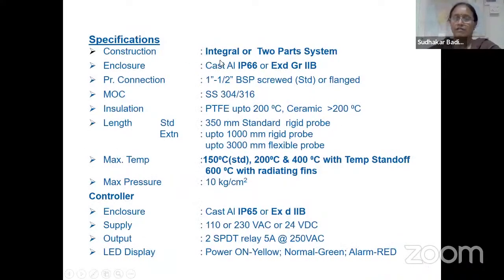It is available in two constructions, that is integral and two part systems. The picture which we saw is of the integral type. It means the electronics is on its head itself, and in the two part system, the probe will be different and the electronics, or control unit, will be different. The enclosure is IP66 or X-proof 2B. The process connections can be screwed or flange connections. Material will be available in SS304 or 316.